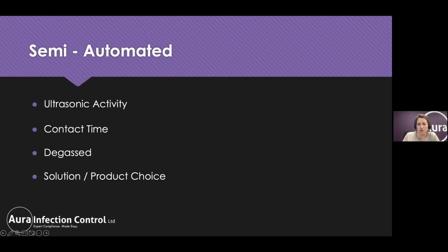A smaller bath with only two or three transducers versus a much bigger bath, you will have a difference in cycle time. It'll also vary depending on the level of contamination on your instruments, the material of instrument, the different type of detergent that you use. So you must make sure that you're validating your cycle time for your practice. Ultrasonic cleaning is a fantastic way of enhancing removal of debris. Although a washer disinfector is preferred, and it should be incorporated into new plans or upgrades, ultrasonic cleaners when we're using them in the right way, when they're fit for purpose, can be very helpful for instruments with hinges or intricate parts. We must make sure we're degassing our ultrasonic baths prior to use to ensure that there's sufficient activity, and items should be briefly immersed in a detergent solution to remove any gross contamination before they go into the ultrasonic bath.